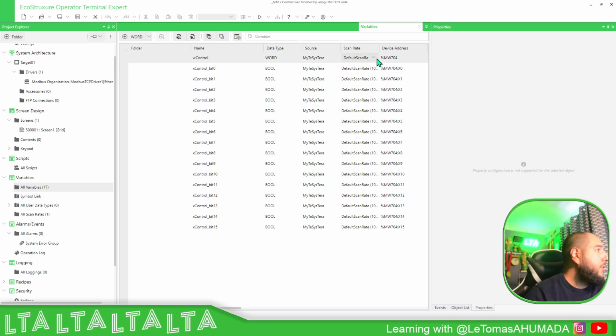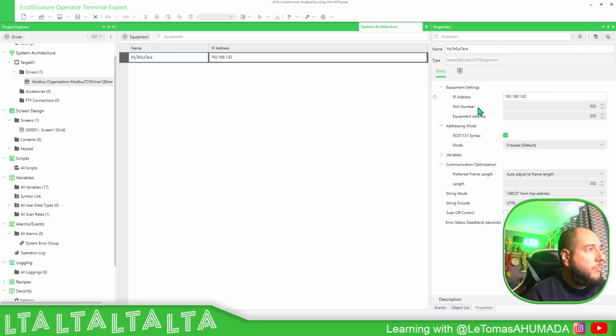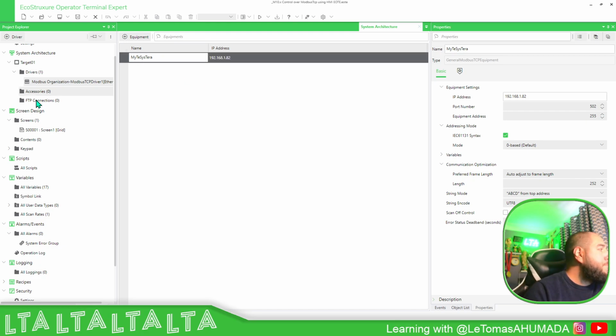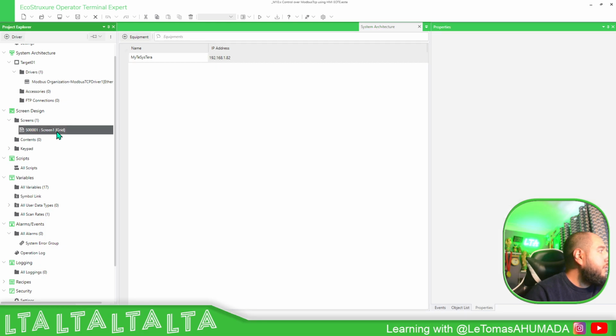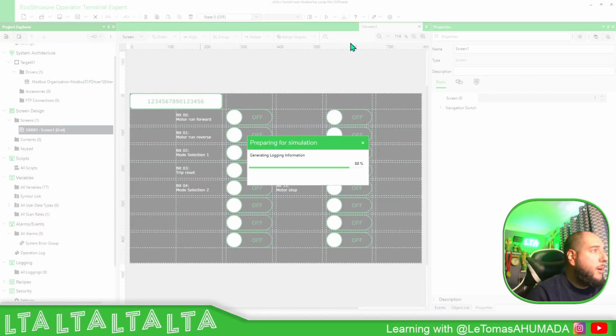I'm pointing to, on the TeSys Tera it is going to be the 705, but here I need to define 704. I need to subtract 1 to the unit, and basically it's based on this because I use base 0. Now that I got this, I have created just one page with all the individual things. So now what I'm going to do is to simulate the device.